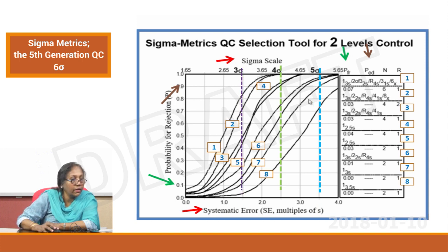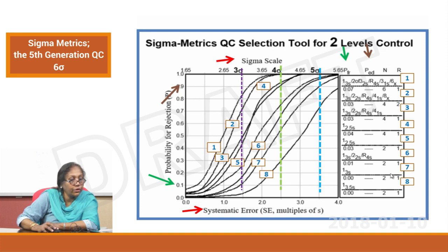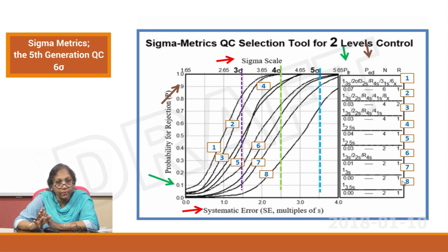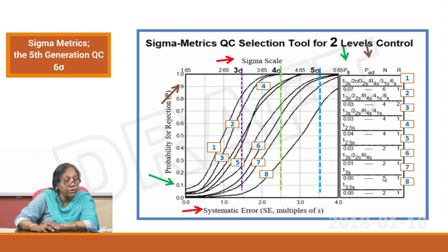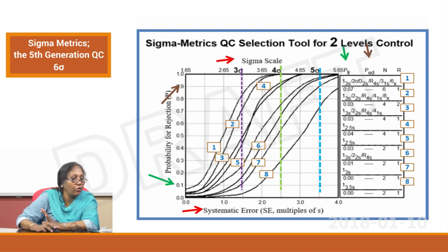Let us look at a few examples. You have a 4 sigma performance here, a 5 sigma performance here, and a 3 sigma performance here. Let us start from 5 sigma: the 5 sigma graph is cutting at graph number 7. For a 5 sigma performance you need to apply only a 1-3S rule — it has no false rejection — and your N should be 2 and your R should be 1. That is how simple it is: if you have a 5 sigma performance, all you need is the 1-3S rule with 2 control levels and 1 run. For 4 sigma: the 4 sigma is cutting graph number 3. Therefore you follow rule set number 3.